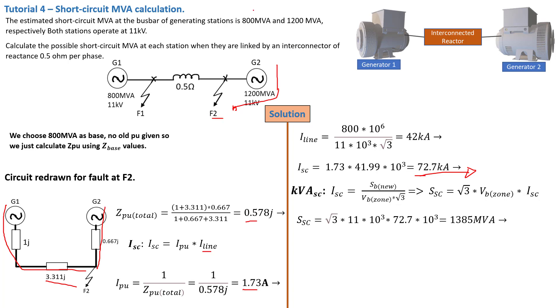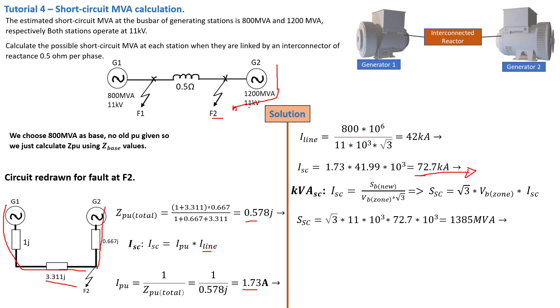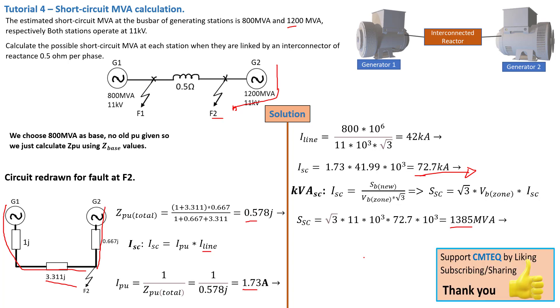Using this current to calculate our short circuit MVA gives us a value of 1385 megavolt ampere. This is higher than the estimated 1200 MVA because we're now accounting for the contribution of G1 into the fault as well. At F1, similarly, the result was 1000 MVA rather than the estimated 800 MVA. That is it for this tutorial. Please don't forget to subscribe to the CMTEQ channel, give this tutorial a thumbs up — that would be highly appreciated. Thank you.